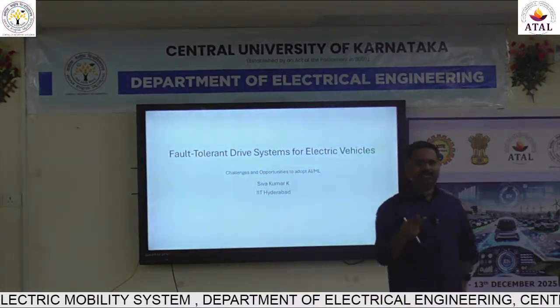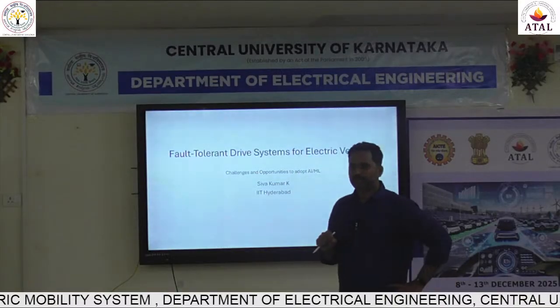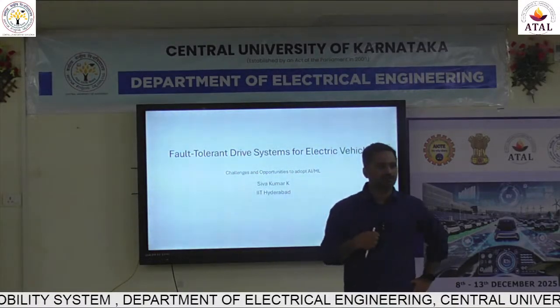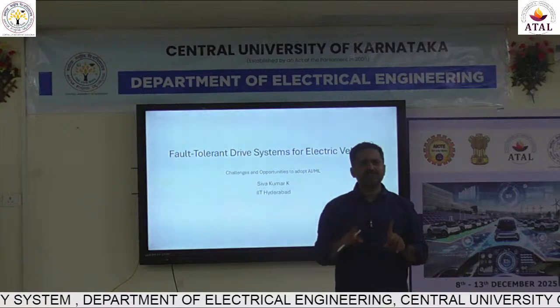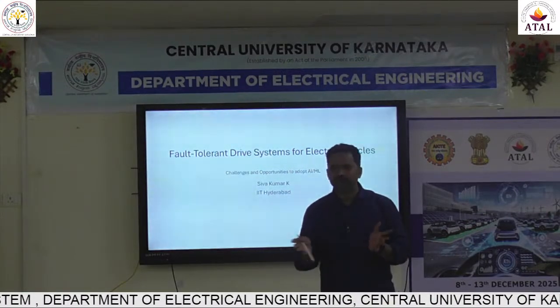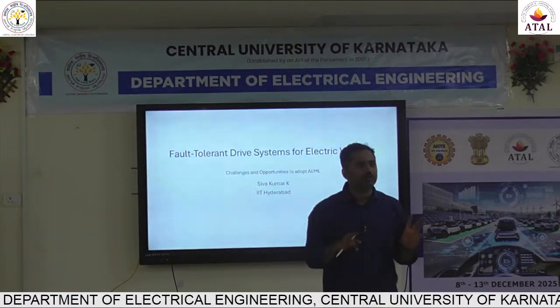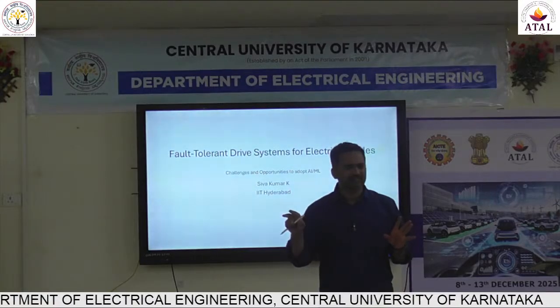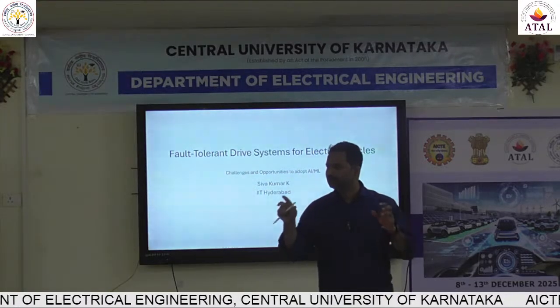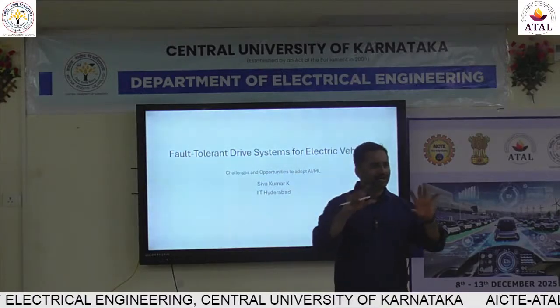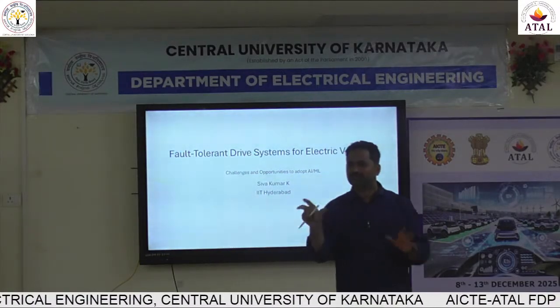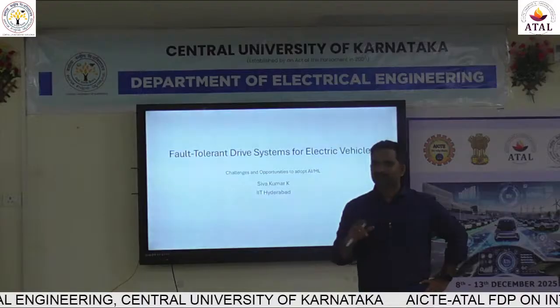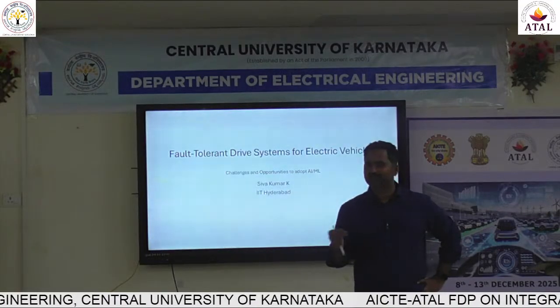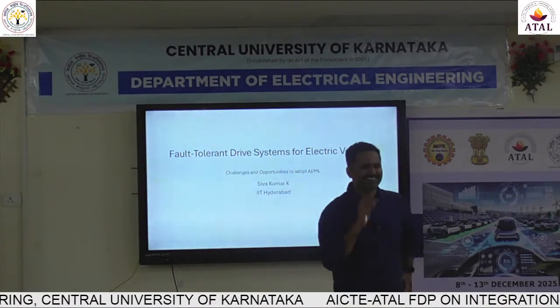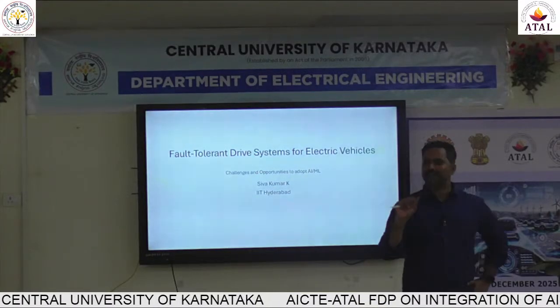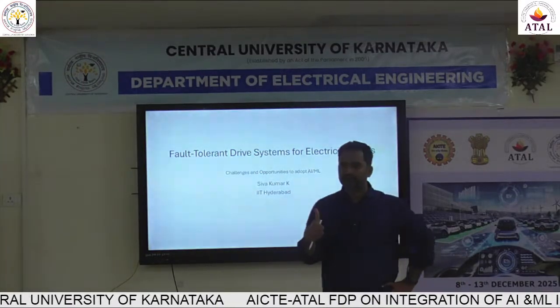The second issue is, if I go with only a 3-phase system, if one of the windings fails, what will happen? Maximum we can run it as open delta. This is what we teach as open delta. The output power can be around 57% something. Correct me if I'm wrong, it was around 56% or 57%. There's 1% here and there because I'm not writing an exam, so I don't remember the numbers exactly. So 56-57%, that's okay, power is fine.